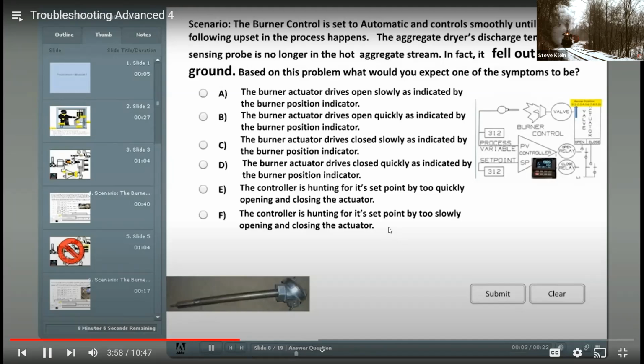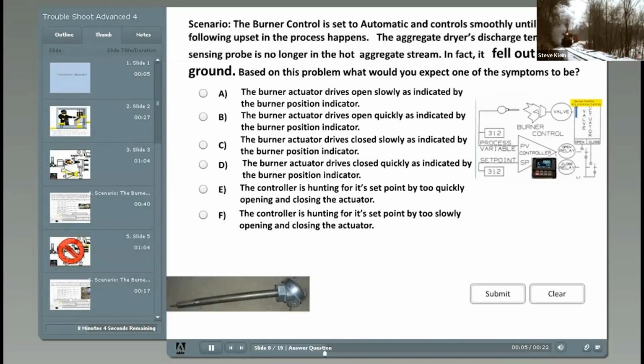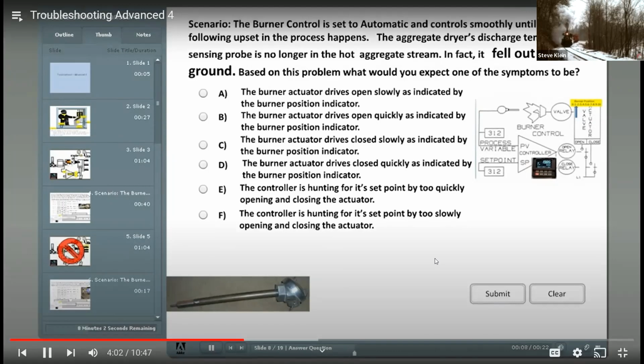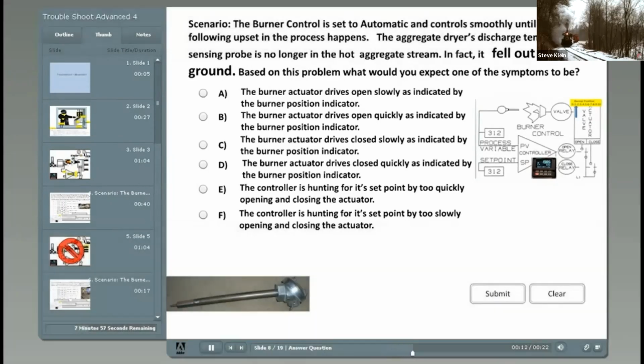The burner control is set to automatic and controls smoothly until the following upset in the process happens. The aggregate dryer's discharge temperature sensing probe is no longer in the hot aggregate stream. In fact, it fell out on the ground. Based on this problem, what would you expect one of the symptoms to be? What do you think, Nathan? I think the controller would be hunting the set point too quickly.